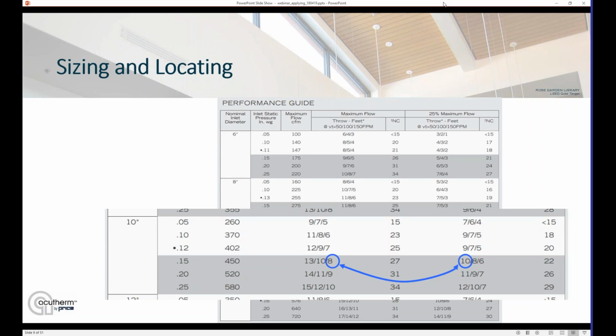And then in the other column there, we look at what's the throw there, the 50 feet per minute throw at the turn down condition, and that's 10 feet. So ideally, this diffuser would be located 9 feet from a wall. Now I realize rooms aren't square. We don't always have a perfect 18 by 18 room, and it's very uncommon for the diffuser to get the center of the ceiling anyway. There's always lighting or sprinklers or PA systems that get into that ceiling first. So you're always going to make some compromise when locating a diffuser.